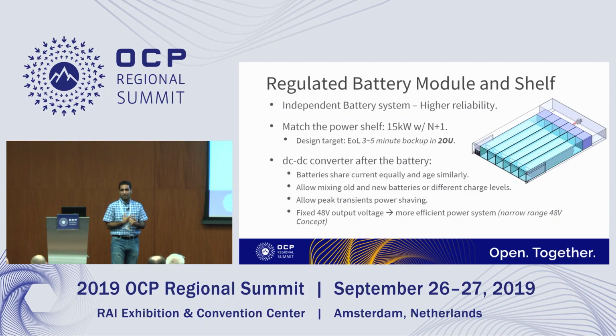And you can allow the mixing of old and new batteries on the same shelf. With an unregulated approach, you always need to match them, so they should always be similar age and similar charge level. At higher scale, data center scale, that could cause problems, but with this approach you don't need to care.